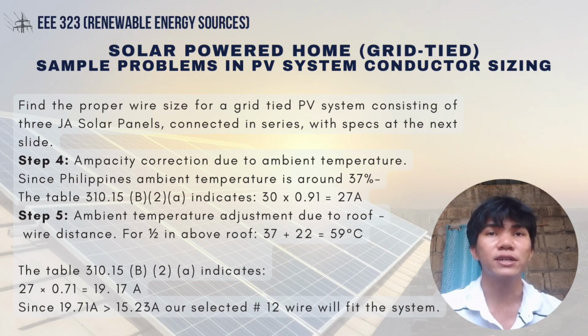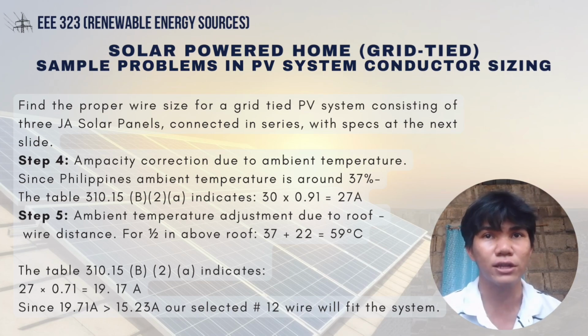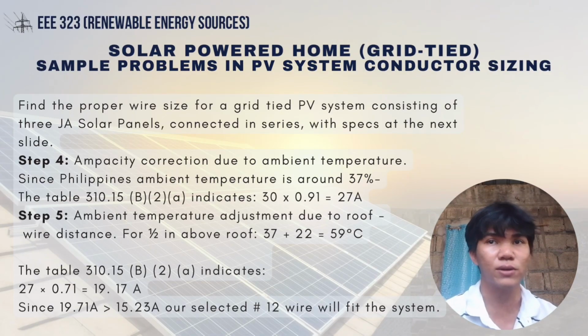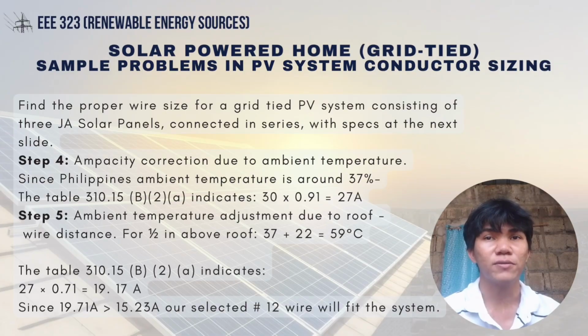For finding the proper wire size for a grid-tied photovoltaic system consisting of 3 JA solar panels connected in series with the specs at the next slide. So, dito tayo sa step 4, for ampacity correction due to ambient temperature. So, since yung Philippines, yung ambient temperature niya is around 37 degrees Celsius. So, in the table 310.15 B2A nag-indicate na 30 times 0.9, meron tayong 27 ampere for new wire ampacity.